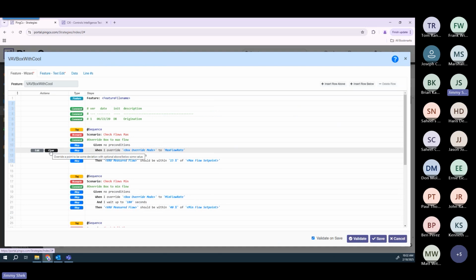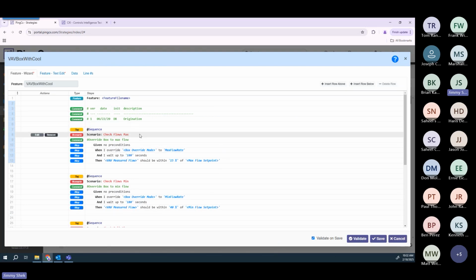So going back to that VAV example, we're looking at this check flow max test scenario. You'll see here, when you write these tests, you're writing it generically, right? And the concept is, once you've written one of these test scenarios, you leverage it over and over for multiple types of VAVs, or from project to project. So in this test scenario, the steps: given no preconditions, when I override the box override mode to max flow rate, wait up to 180 seconds, then the VAV measured flow should be within 15% of the max flow set point.